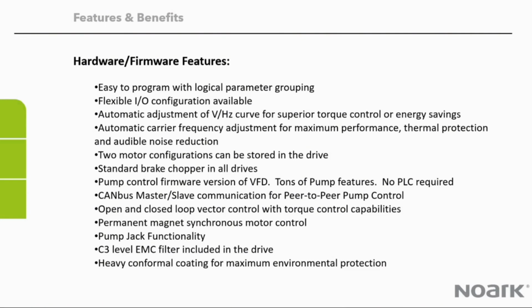They monitor that for thermal protection to make sure we don't overheat the transistors. And it also reduces the audible noise. I was at a customer running a compressor, and some of their folks came by and did not believe the drive was running. It was that quiet. So normal singing will be minimized with our drive.